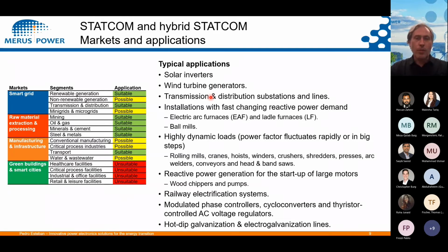Ralph will talk later about the transmission and distribution applications in high voltage. Any big installation that has fast changing reactive power demand, or loads that are very dynamic, also has very good application for STATCOMs. It can be used even for compensating the startup of large motors, railway electrification systems, and so on.